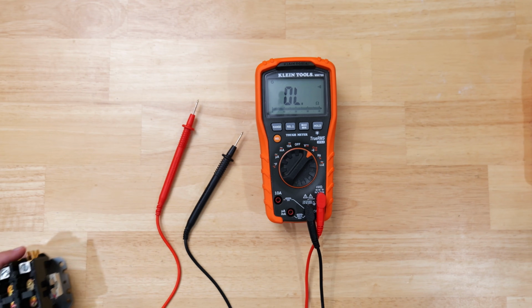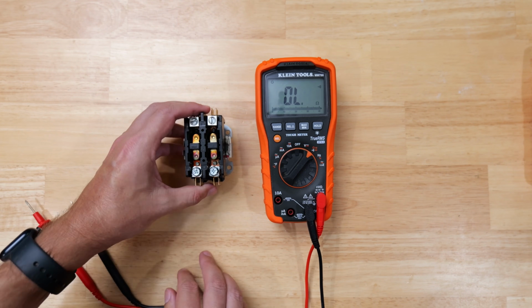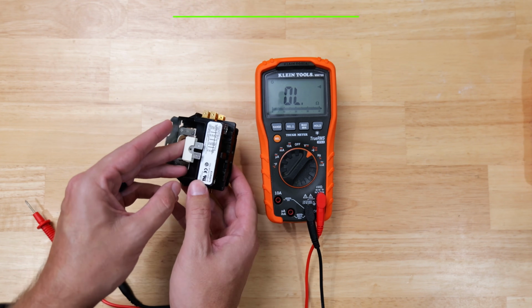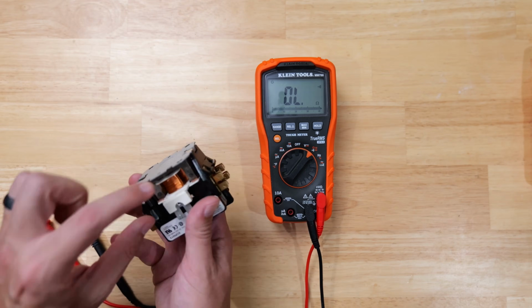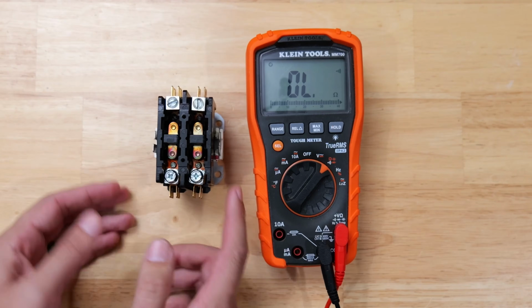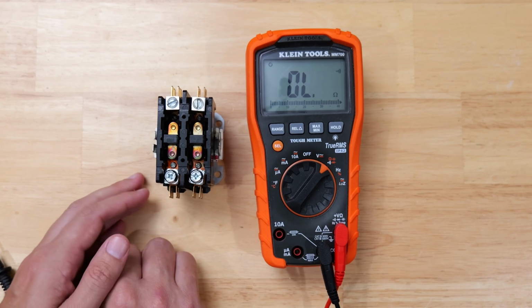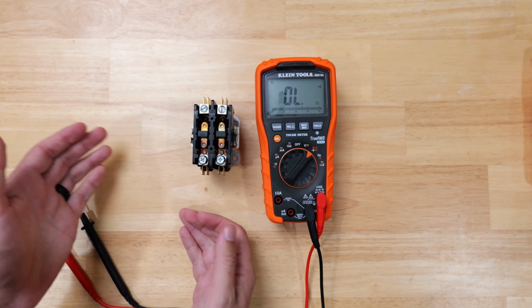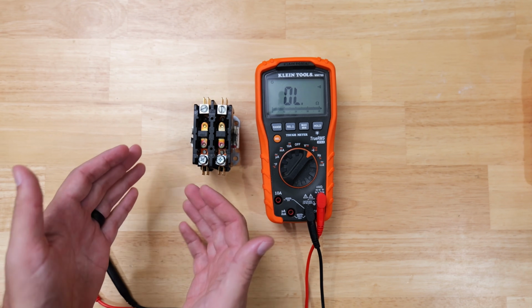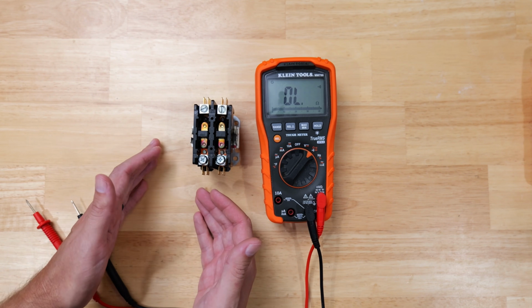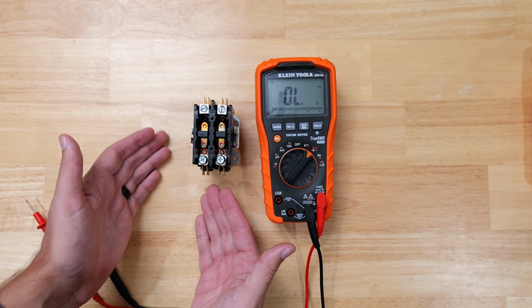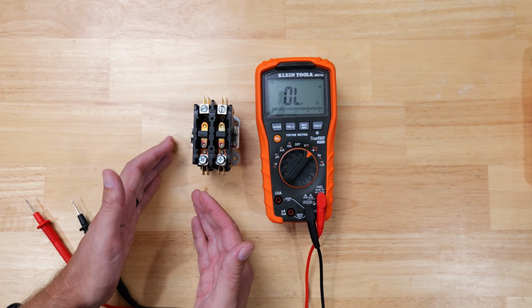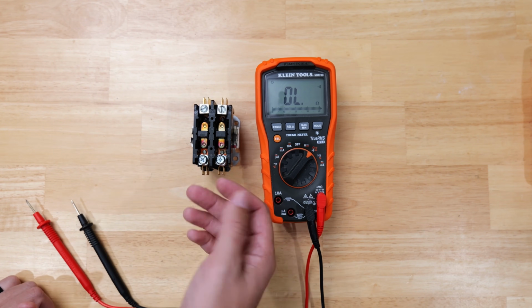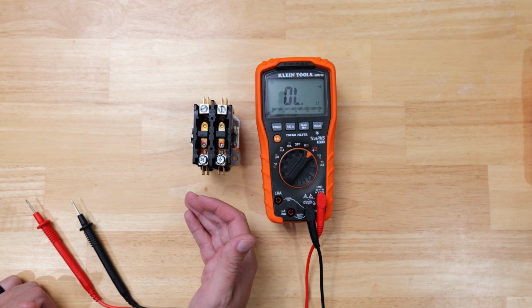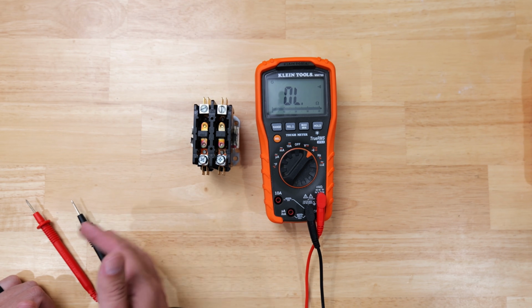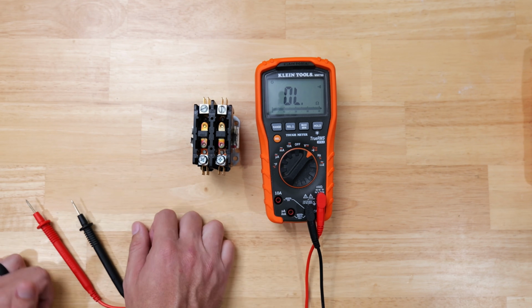This can come in really handy. Take this AC contactor, for example. There's a coil between these two sides, and this is somewhere I've used this test personally. You can use it with water heaters and in a lot of other applications. As long as you know what your resistance reading should be, it can really help with troubleshooting. A lot of times you can find that resistance reading on the data sheet for whatever it is you're testing.